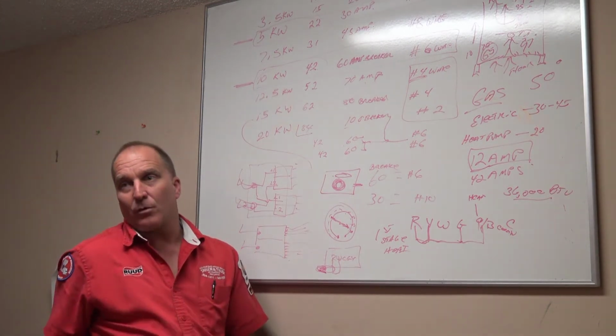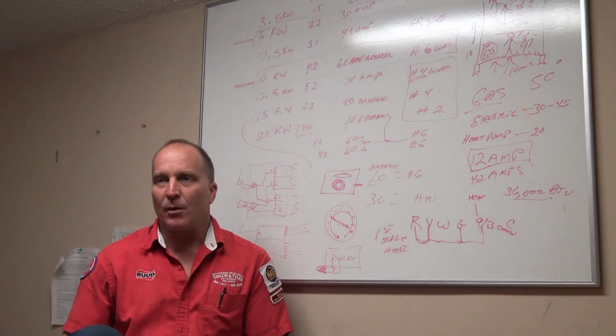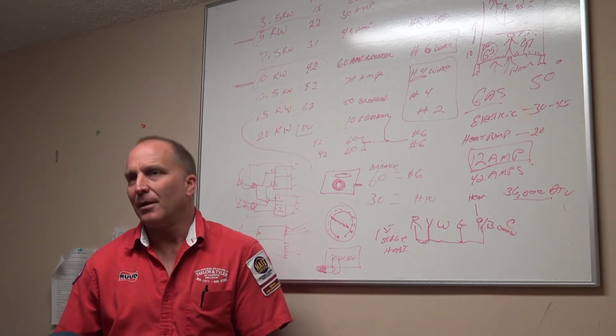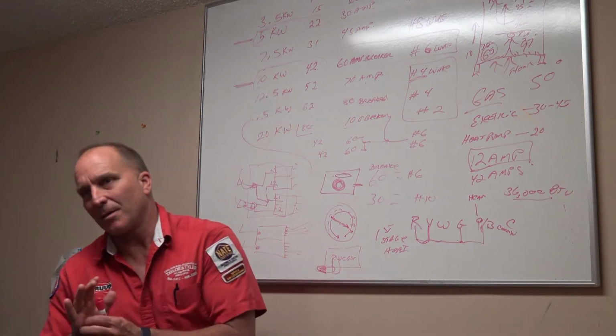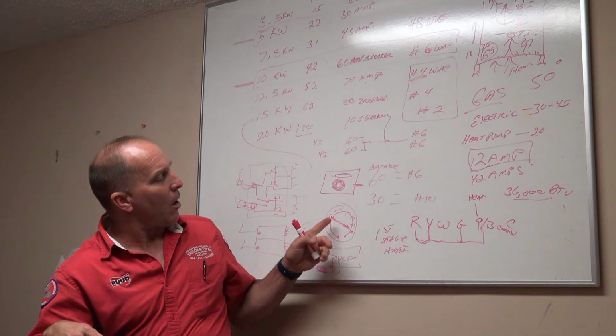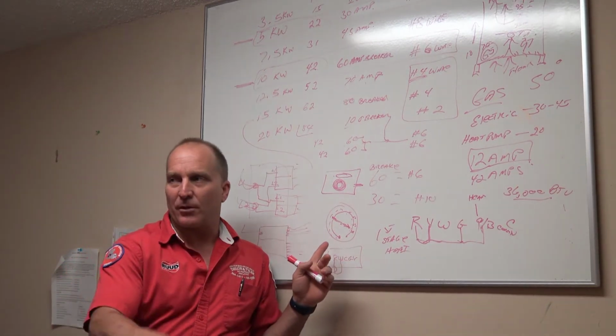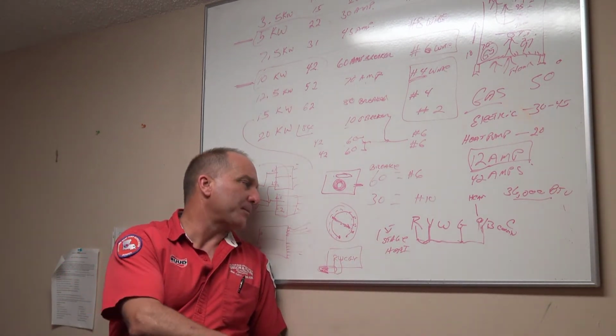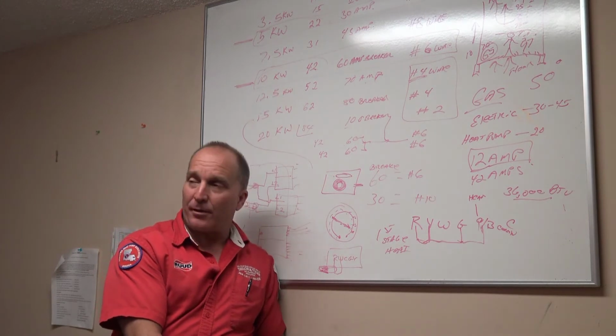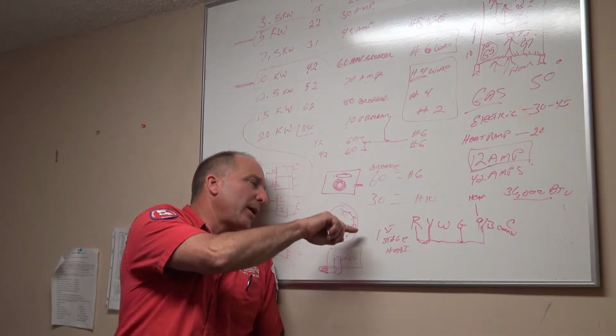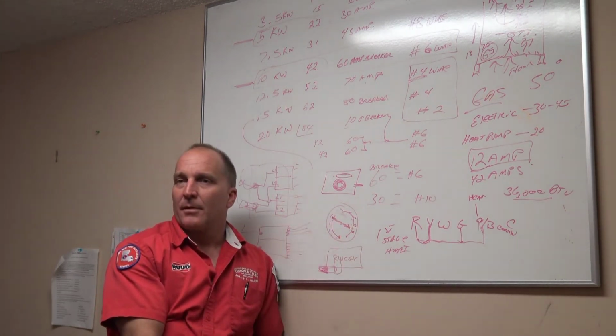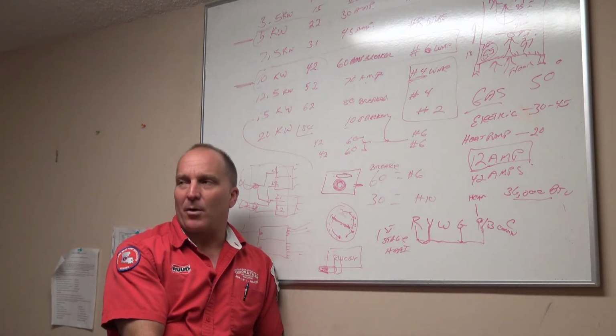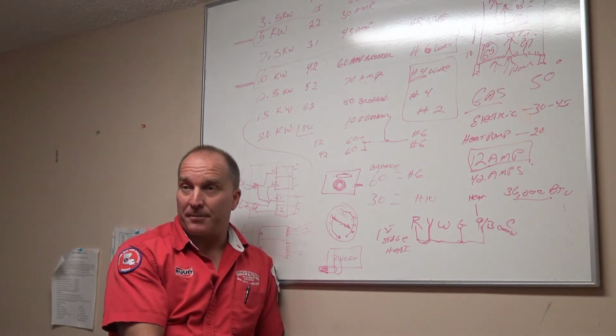The heat anticipator will then tell that thermostat when to turn the heater on and when to turn it off. It will not turn on and off by temperature; it turns on and off by the heat anticipator. So if you set this wrong, it will not come on and off at the right temperature. Next thing, if you short that thermostat in any kind of way, you will break this wire. When you break that wire, your heater will not come on anymore. You have to replace the thermostat.